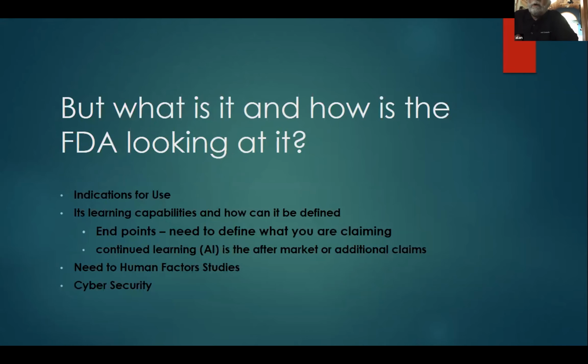As part of your submission, the FDA is going to want to see: does the device need human factor studies? How is the device being used? What is the clinical use of the device, will they be able to use it, how is it going to be worked? They want to make sure that it's going to be able to be used by the medical community. And the last thing that the FDA really keys into is cybersecurity, which we all know is an area of concern in getting medical data out and controlling that medical data.